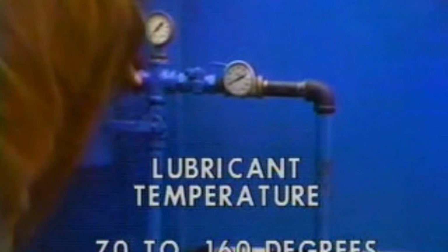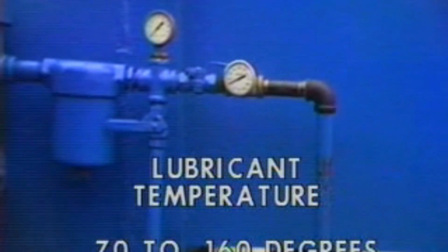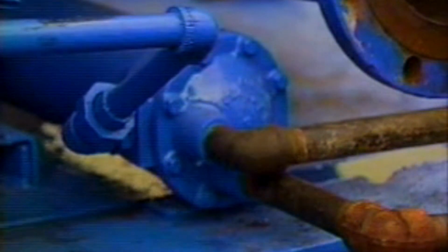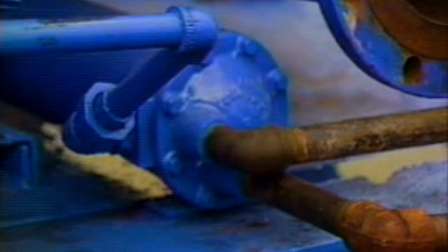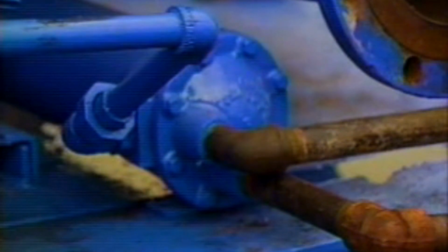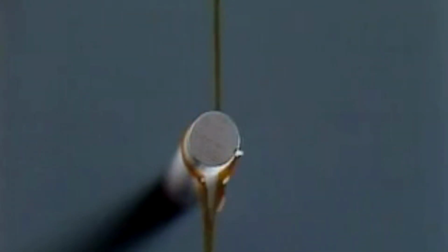If your pump has an oil temperature gauge, check it daily to ensure that the oil is within the accepted range, between 70 and 160 degrees Fahrenheit. If the temperature is above or below these limits, make sure you aren't bypassing the heat exchanger. If that's not the problem, you may need to heat or cool the liquid feeding the exchanger. If you let the lubricant get too hot, it'll get too thin and soon break down. If it gets too cold, it won't flow to the parts that need it.